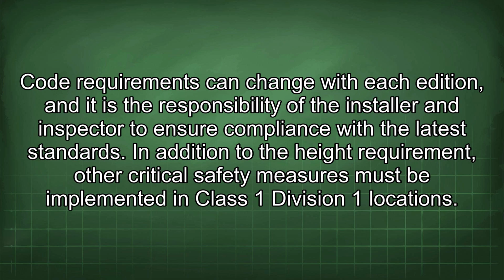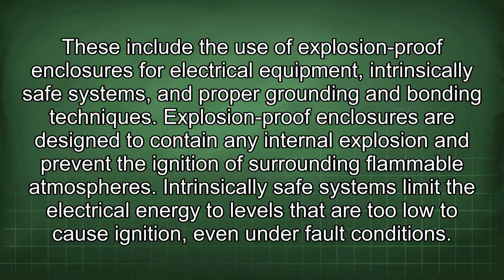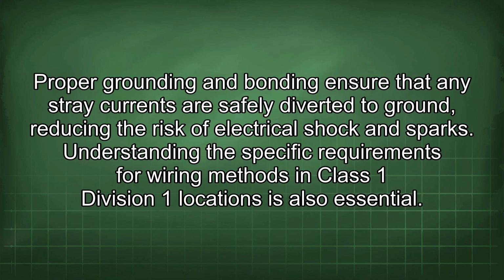In addition to the height requirement, other critical safety measures must be implemented in Class 1 Division 1 locations. These include the use of explosion-proof enclosures for electrical equipment, intrinsically safe systems, and proper grounding and bonding techniques. Explosion-proof enclosures are designed to contain any internal explosion and prevent the ignition of surrounding flammable atmospheres. Intrinsically safe systems limit the electrical energy to levels that are too low to cause ignition even under fault conditions. Proper grounding and bonding ensure that any stray currents are safely diverted to ground, reducing the risk of electrical shock and sparks.